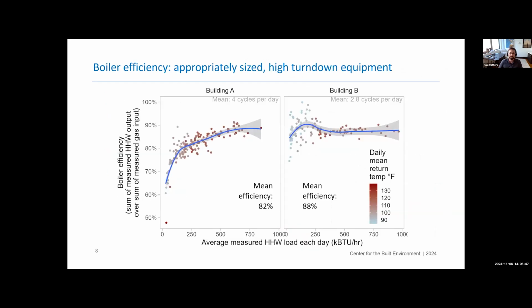So we did that in some other buildings where we installed boilers and we really aggressively sized these boilers. They are half the size of the existing boiler plant. And we put in two of them and they have 20-to-1 turn down. So these pieces of equipment really are pushing the boundaries of how you would size equipment. And even in these two buildings, they're slightly below the nominal efficiency compared to the manufacturer test data, because that test data is really set up in a way to be repeatable and steady state, but it doesn't really capture some of the losses that occur in real buildings. Like, for example, when you turn a boiler plant off at night and it cools down, you have to heat it back up again. There are some losses there.